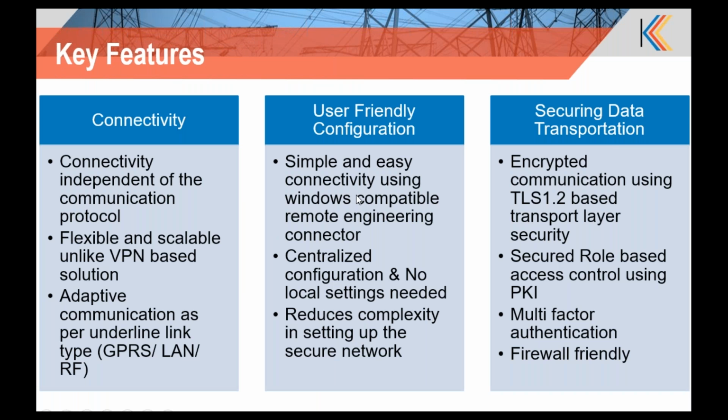So the configuration is done centrally, and all the central configuration can be accessed from a web browser. User can directly go to the web browser, log in, get the device you want to connect to, click on the device, and initiate the remote connection procedure, which will automatically launch the remote connector in his laptop and establish a secure tunnel from his laptop or the engineering PC up to the end devices, if that user has got the privilege to access the device.